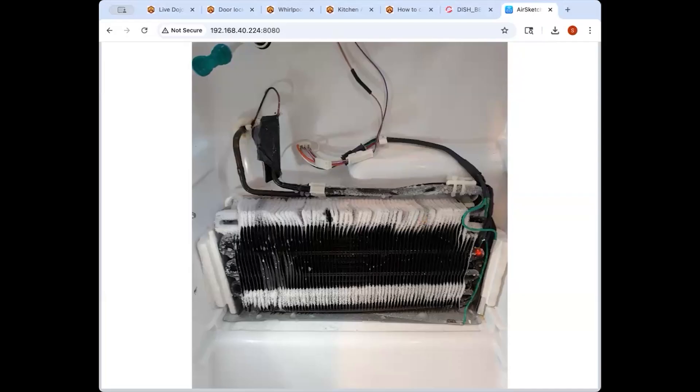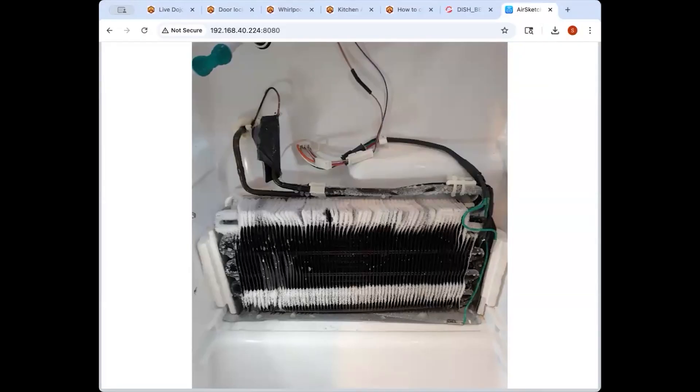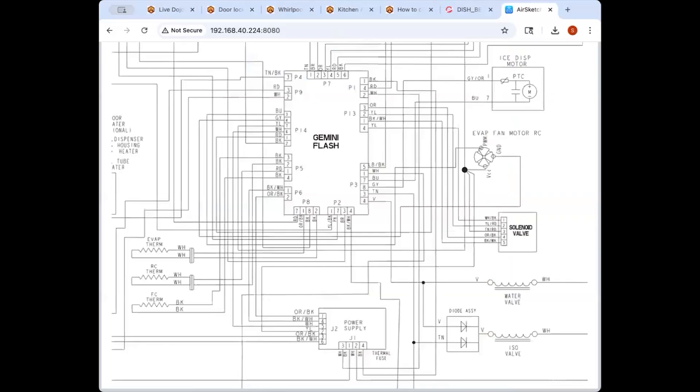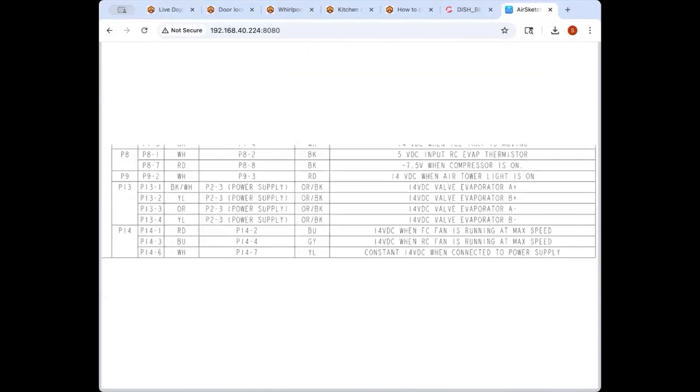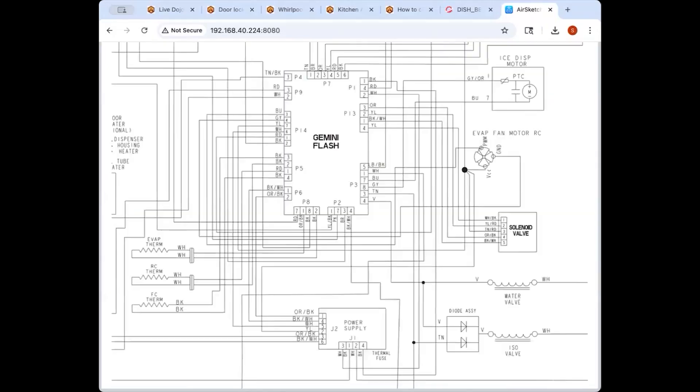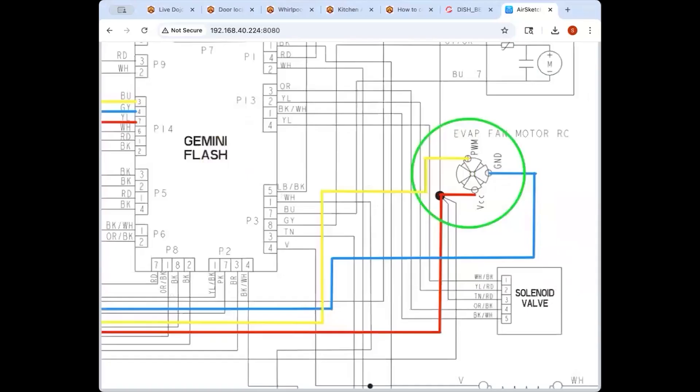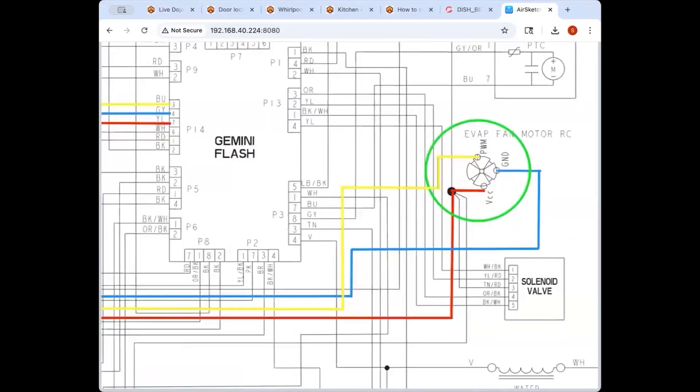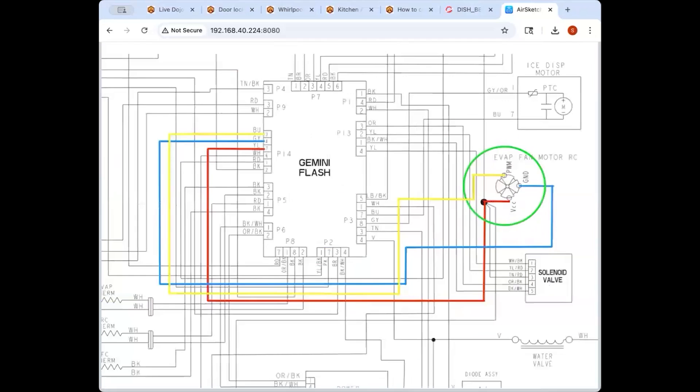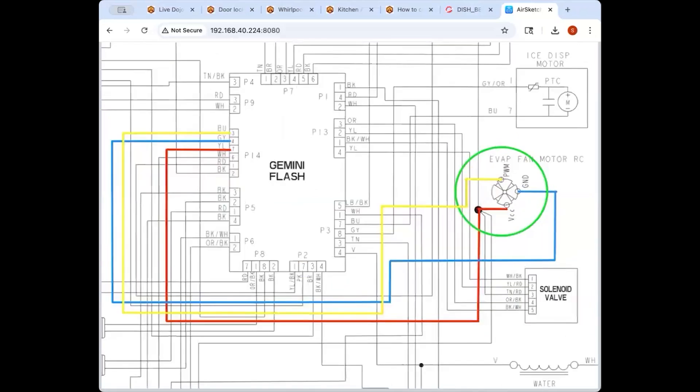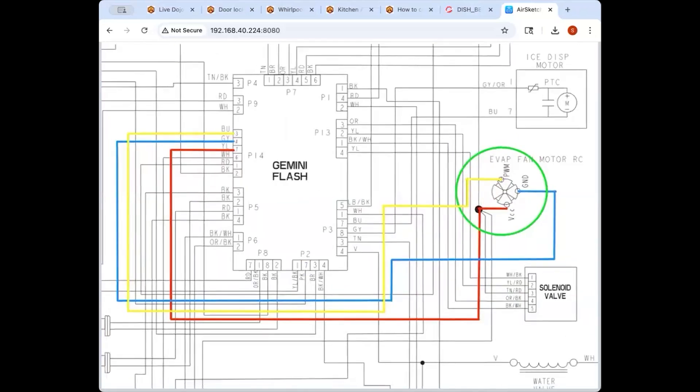When he took off the cover this is the frost pattern on the evaporator. So this guy did some really solid troubleshooting. First thing he did, he went into test mode and started testing loads. He put the evaporator fan into a forced run mode and it did not run. Then while in that forced run mode he went to P14 on the board and checked for the various inputs that he's supposed to get going to that evaporator fan.